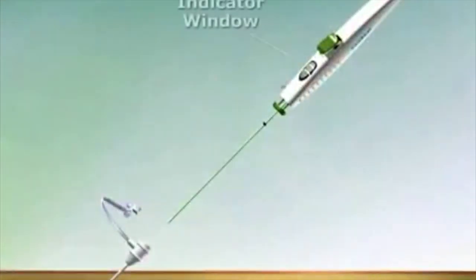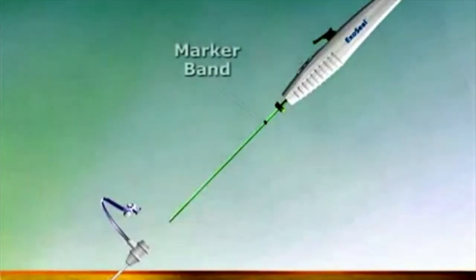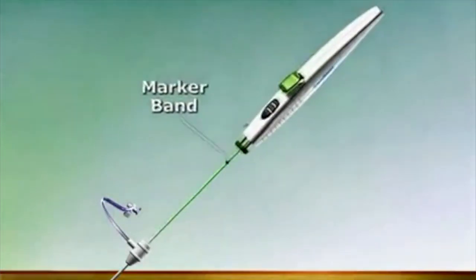Orient the device so that the indicator window on the handle faces upwards. Insert the delivery shaft into the femoral sheath up to the marker band on the delivery shaft.